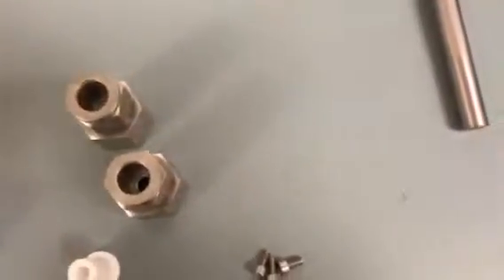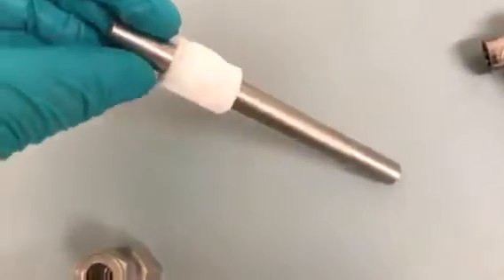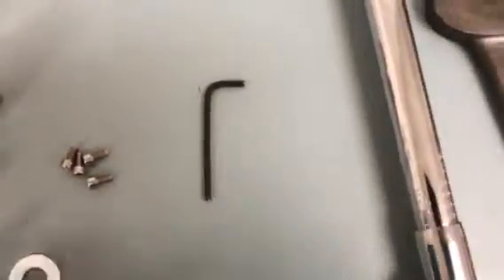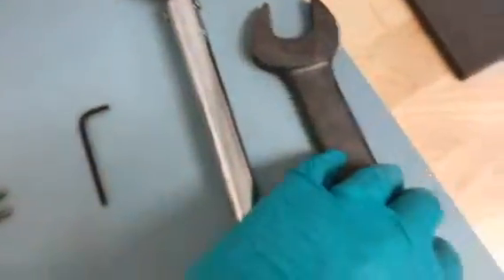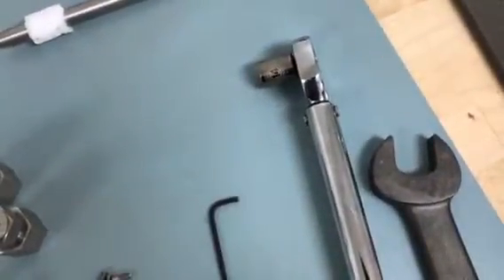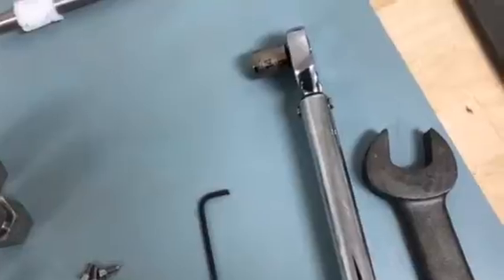One is a lip seal insertion tool. This is a storage rod for the lip seals, just shown as reference. We have a 3mm Allen key. Z-Axis does recommend a torque specification, which I will note when we install the M4 screws. We have a torque wrench and an open end wrench, and we'll be able to assemble the sanitary pump head as well as disassemble. So let's get started.